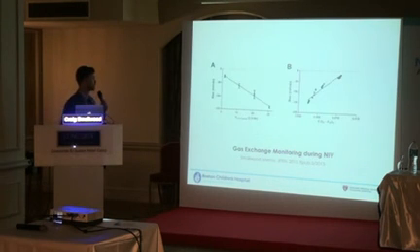And this is the same data in a different plot, but we just looked at the amount of air that was entrained in excess of that which was set. And basically the bias was limited the closer to zero those two numbers were. So the reduced difference meant improved accuracy.